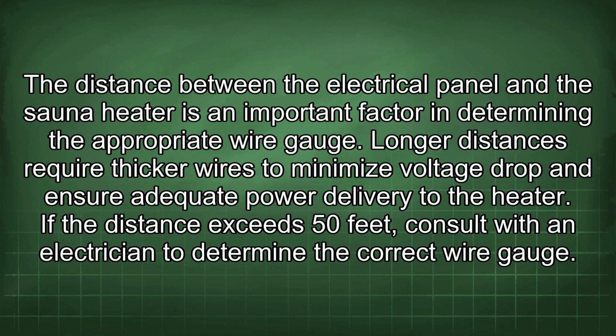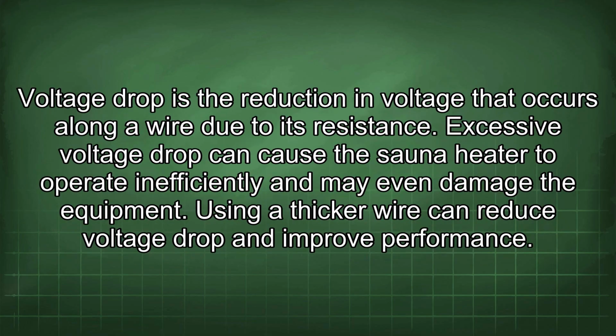The distance between the electrical panel and the sauna heater is an important factor in determining the appropriate wire gauge. Longer distances require thicker wires to minimize voltage drop and ensure adequate power delivery to the heater. If the distance exceeds 50 feet, consult with an electrician to determine the correct wire gauge. Voltage drop is the reduction in voltage that occurs along a wire due to its resistance. Excessive voltage drop can cause the sauna heater to operate inefficiently and may even damage the equipment. Using a thicker wire can reduce voltage drop and improve performance.